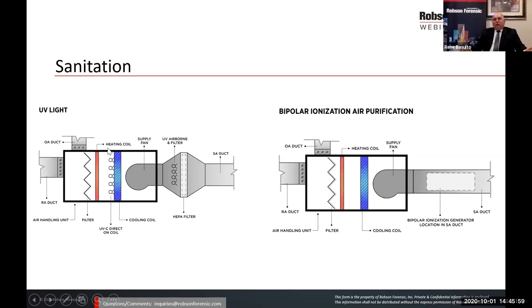You'll see that you have to get into the unit itself to get it in, and it requires a little bit of work. The bipolar ionization is a bit simpler process. You still have the same unit, the same process inside the unit. And this is basically just a device. You have your bipolar emitter at the discharge inside the ductwork, where you're just basically plugging it in, and that's ionizing the air coming across and hopefully neutralizing bacteria within the space, bacteria, viruses, whatever it may be.